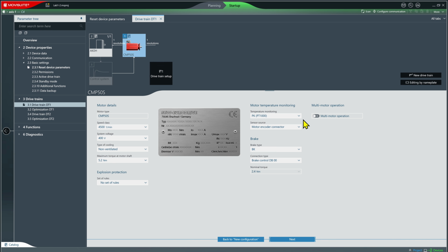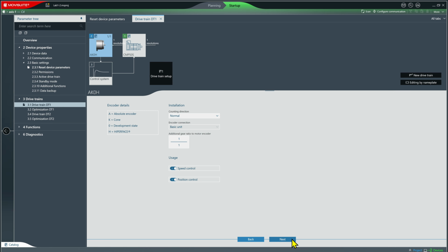My temperature monitoring is okay. It is connected up to my VFD through the motor encoder connector, that is fine. My brake is correct, the way it's controlled is correct. So we're in good shape now. We'll go ahead and click the next button, and that asks us about our encoder, and we're not going to change anything here. All the default settings are just fine, so we click next.